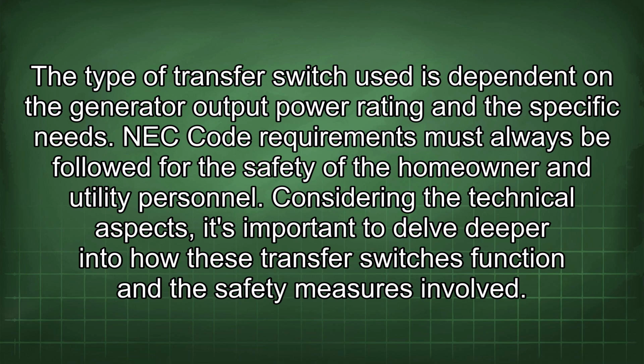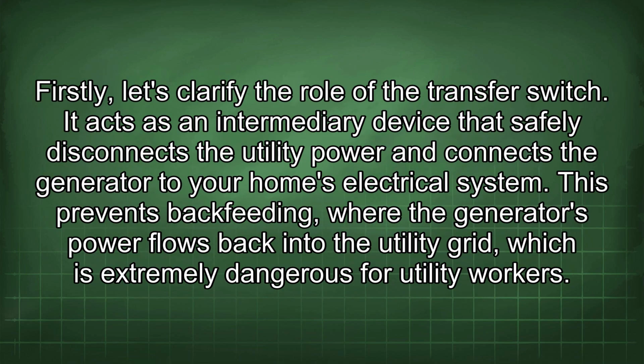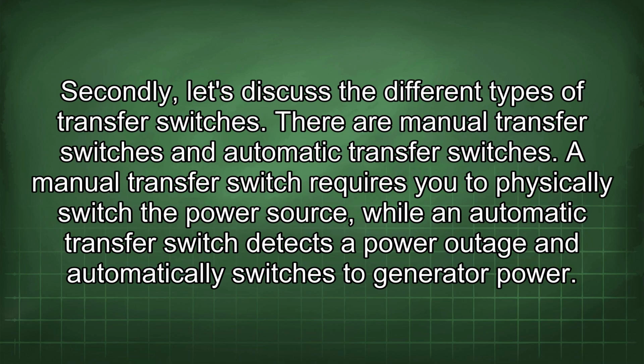Considering the technical aspects, it's important to delve deeper into how these transfer switches function and the safety measures involved. Firstly, let's clarify the role of the transfer switch. It acts as an intermediary device that safely disconnects the utility power and connects the generator to your home's electrical system. This prevents backfeeding, where the generator's power flows back into the utility grid, which is extremely dangerous for utility workers.